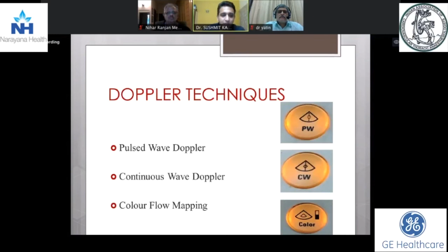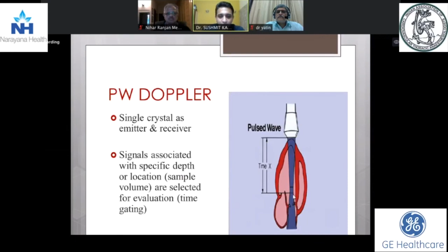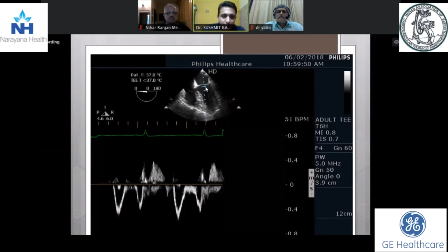Pulsed wave Doppler uses a single crystal as an emitter and a receiver. So signals at a specific depth or location are evaluated, and this is known as the sample volume. For example, if you want to study the transmitral flow, we need to place the sample volume between the mitral leaflets to get an accurate reading. Since there is a repeating pattern of ultrasound transmission and reception, and both are not happening at the same time, it is dependent on the pulse repetition frequency, that is the rate at which the device repeatedly generates the sound bursts.